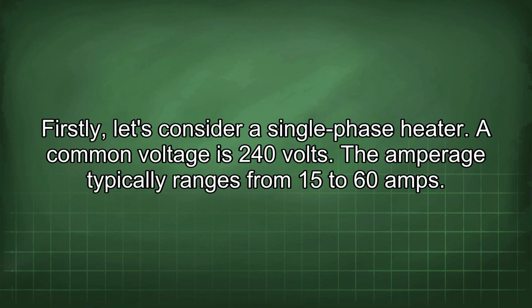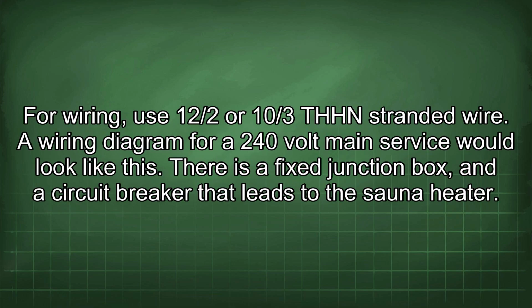Firstly, let's consider a single-phase heater. A common voltage is 240 volts. The amperage typically ranges from 15 to 60 amps. For wiring, use 12/2 or 10/3 THHN stranded wire.